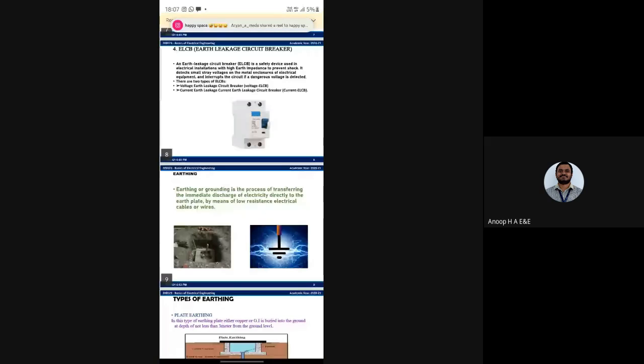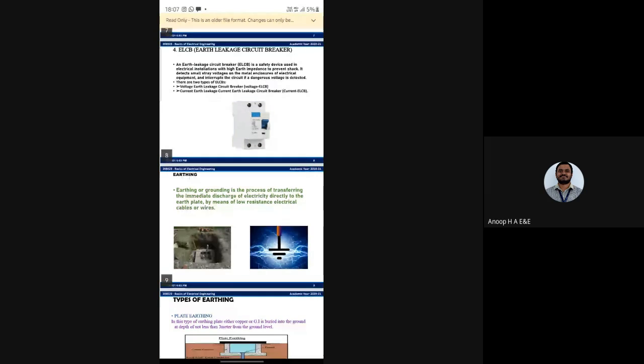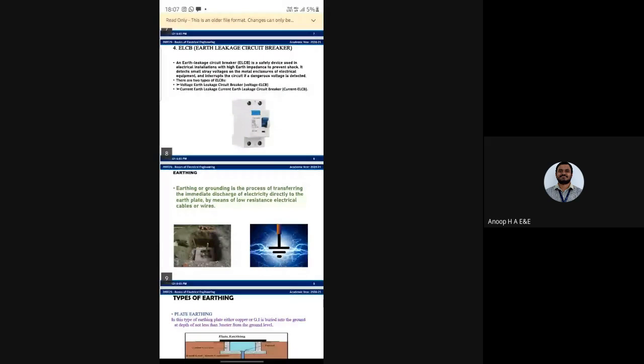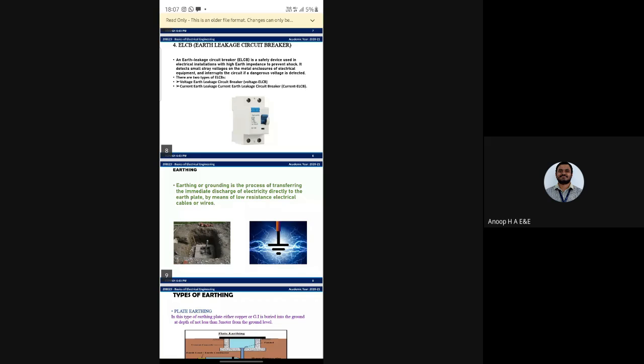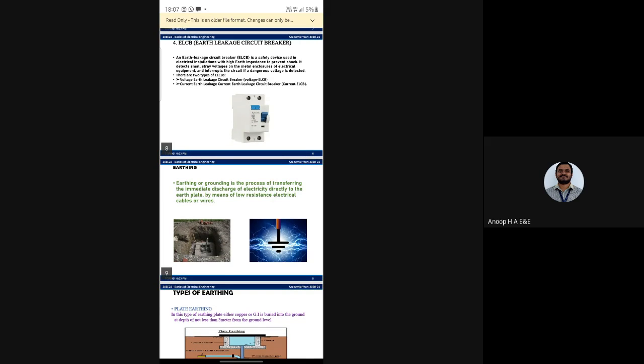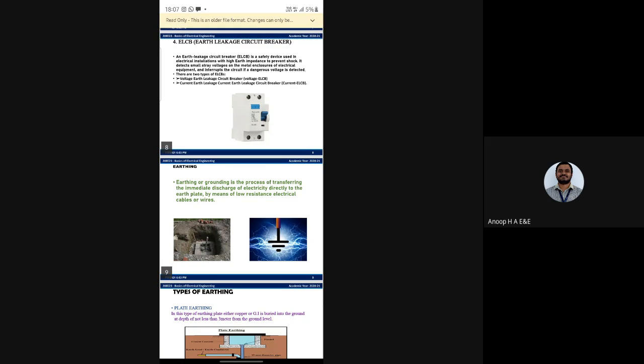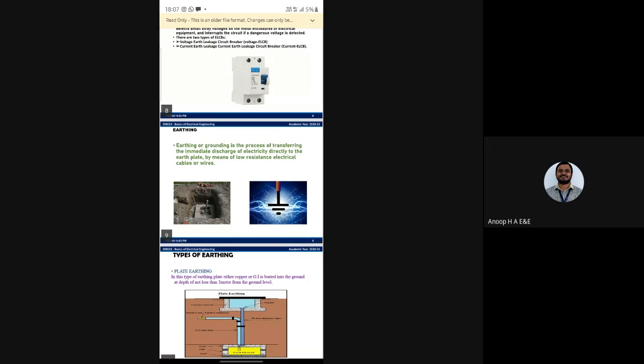ELCB, Earth Leakage Circuit Breaker. An earth leakage circuit breaker is a safety device used to detect small leakage voltage on metal enclosures of electrical equipment and interrupts the circuit if dangerous voltage is detected. There are two types of ELCBs: the voltage earth leakage circuit breaker and the current earth leakage circuit breaker.